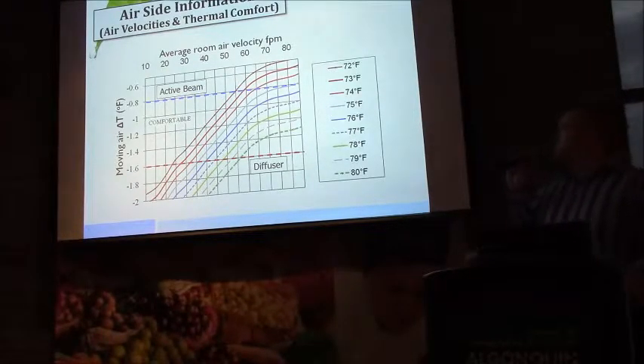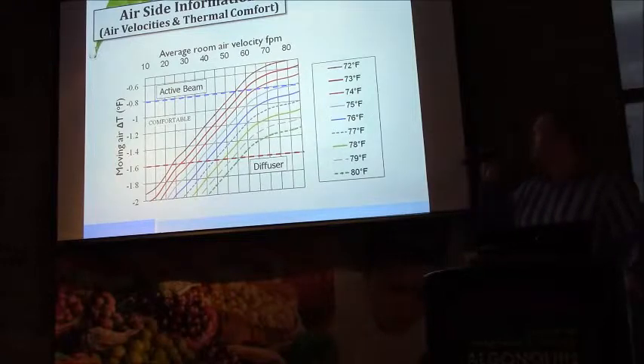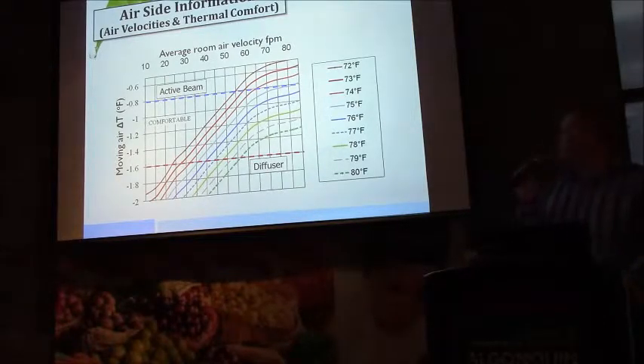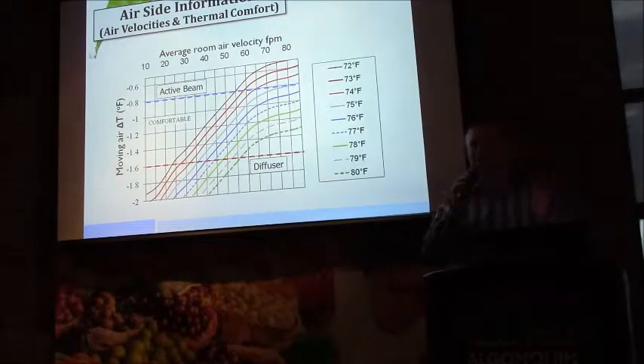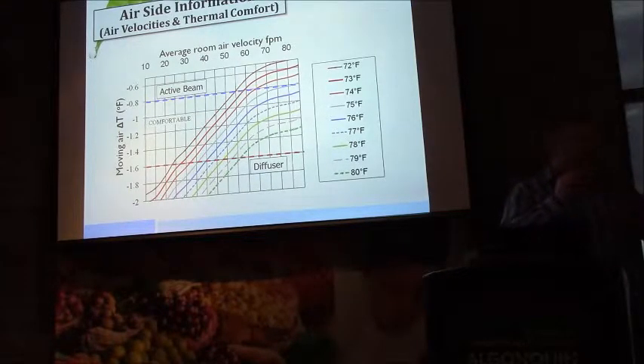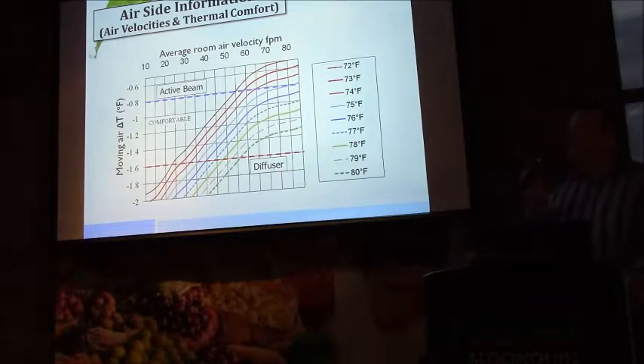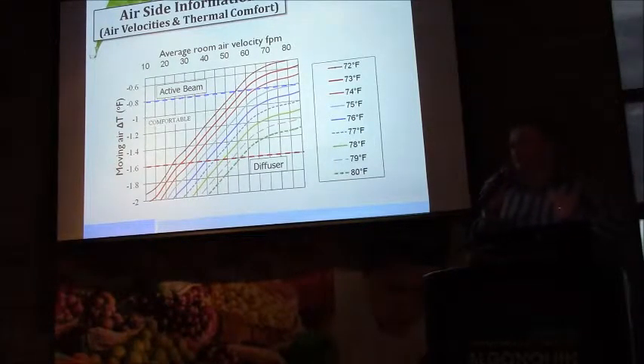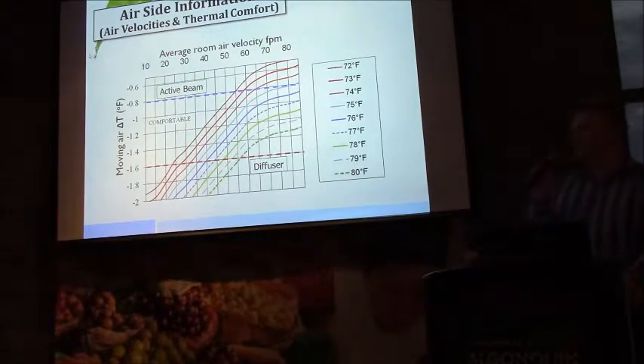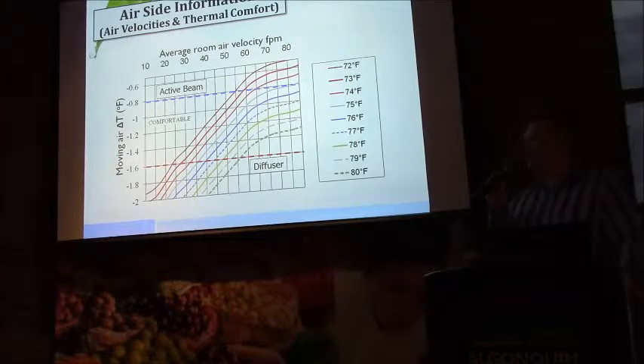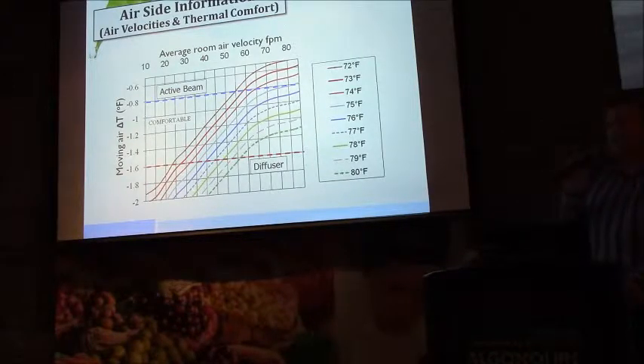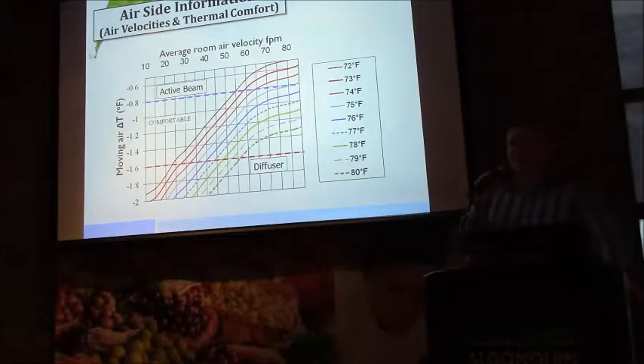However, under the design condition of an active beam solution, where we're designing the space to a warmer temperature to begin with, and as a consequence of the fact that the primary air is mixed vigorously within the body before it's discharged to the space, that same position where we're measuring the temperature variations in the space would net an observed temperature variation of less than 1 degree Fahrenheit. This suggests that we could conceivably push the average room air velocity to as high as 70 to 80 feet per minute.